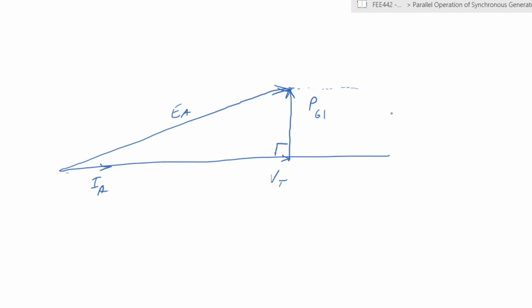Now, in this particular case, if we change the governor set points such that you are now supplying a higher power, so let's say you are supplying at PG2, that means your terminal voltage will remain the same, because you're connected to an infinite bus bar. Your machine has to remain at that terminal voltage, but you want it to produce more power. What options do you have?